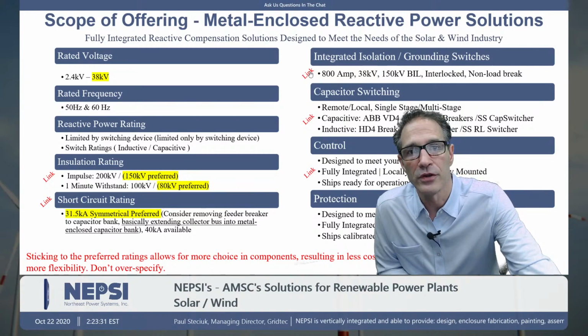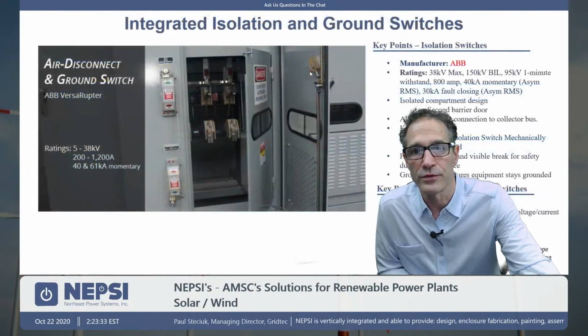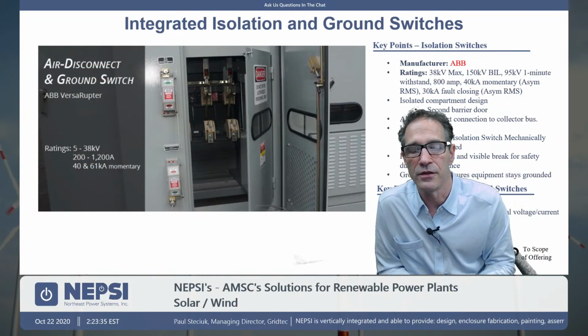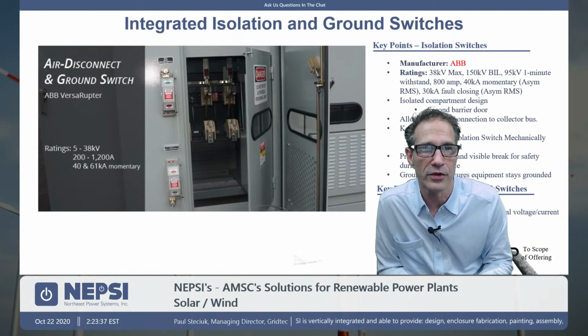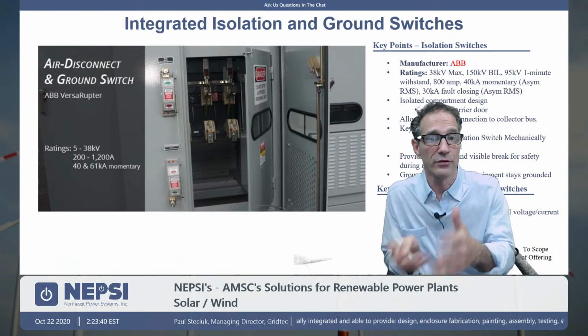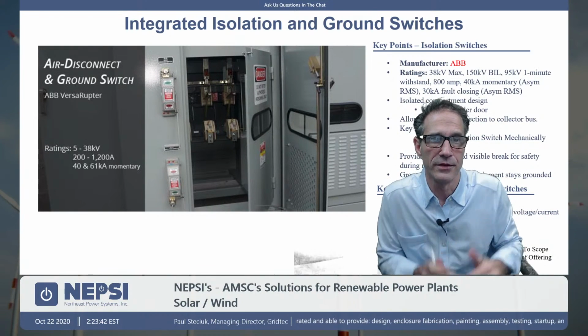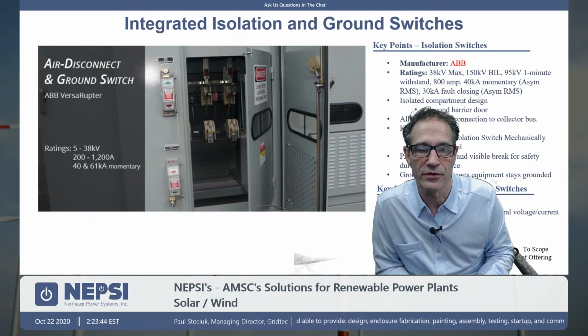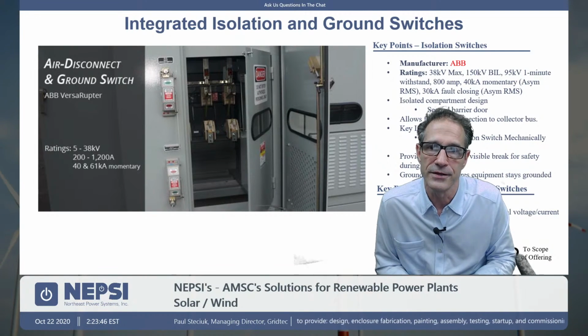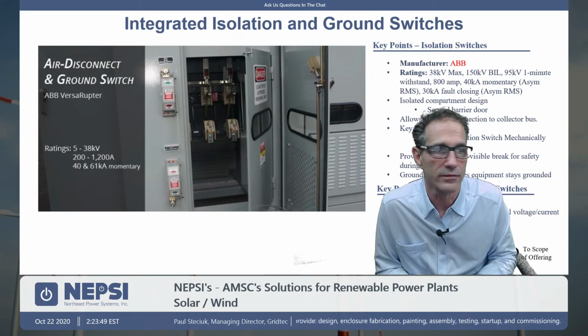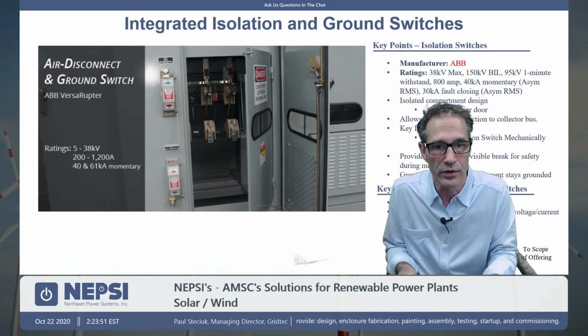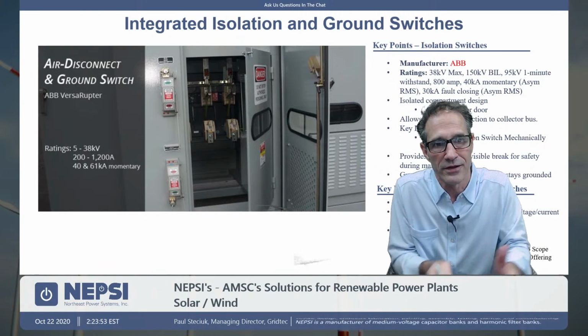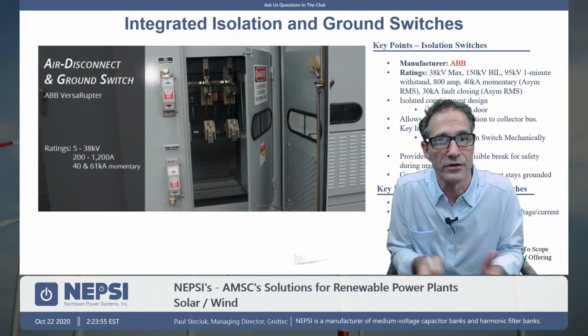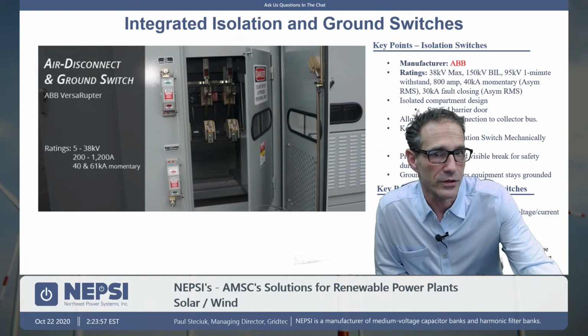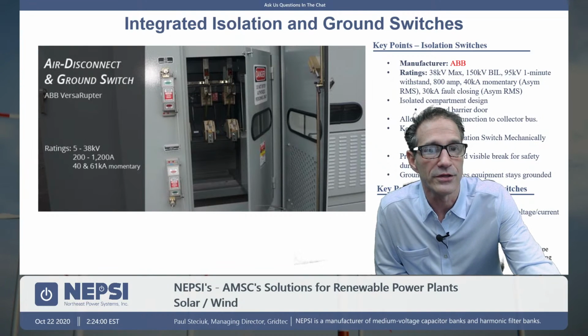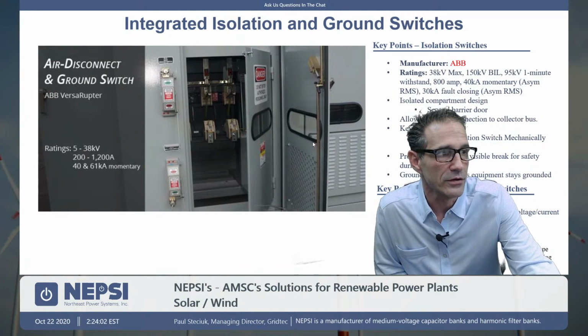We could put an integrated isolation switch in our equipment too. We have an ABB 38 kV VersaRupter that we can put into our equipment. And basically what that does is it's going to eliminate the upstream disconnect that you might have in the substation. So we're going to show also how that can save on cost. But basically what we're doing is we're putting more into our package and you're putting less into the main substation. So it's more of an integrated solution and reducing costs, reducing site costs, installation costs, purchasing costs, and so on.